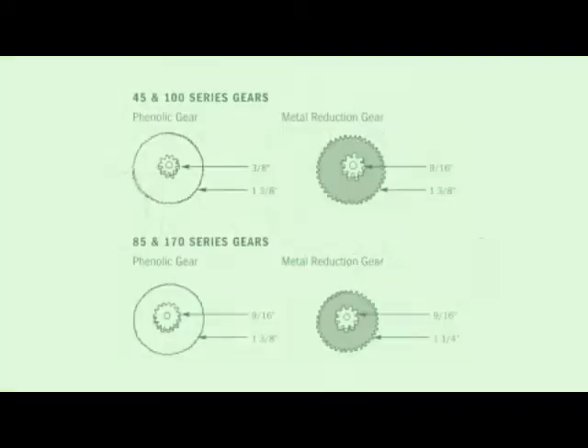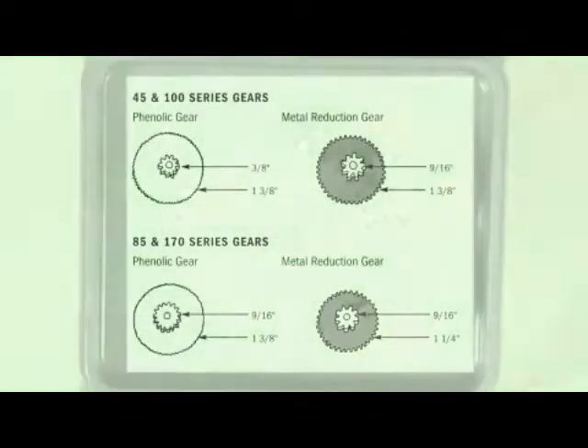The Classic Series motor is a gear motor, and the motor shaft with gear drives the feed rate control. Located in the gear case is the metal reduction gear and phenolic gear that control the RPM of the feed rate and pump head. The 45 series delivers approximately 26 RPM and approximately 44 RPM for the 85 series. The illustrations show the diameters of the gears and pinions.